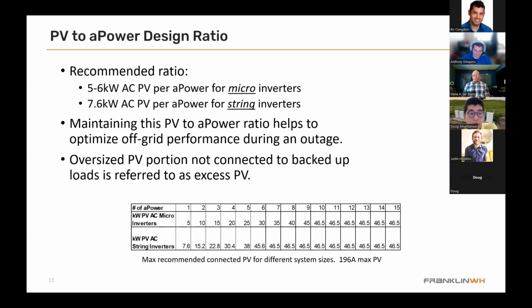About 5 to 6 kW PV per aPower for microinverters, and about 7.6 kW PV for string inverters. Within about a month, we're going to make it 7.6 kW for both micro and string. Maintaining this PV to aPower ratio helps make sure that if you do have an outage, the system is as stable as possible and performs, because the homeowner's paying quite a bit of money.